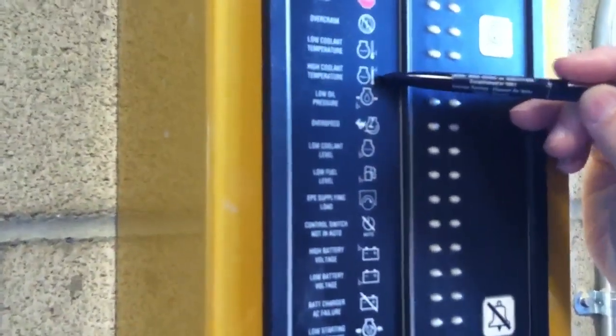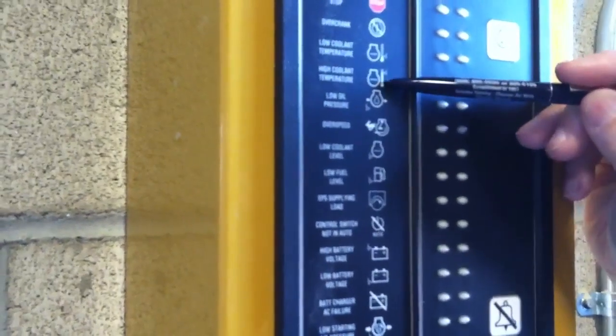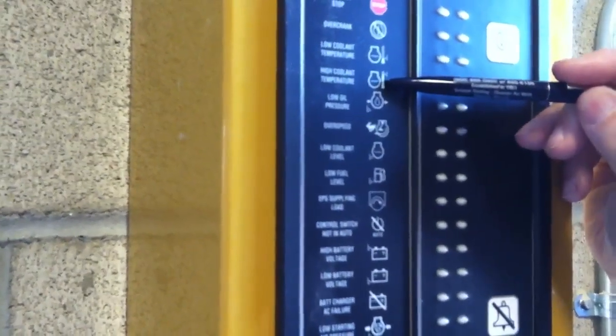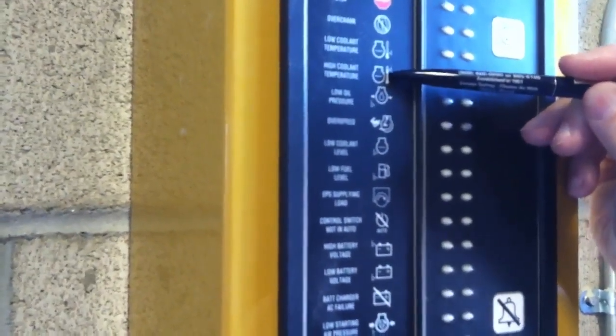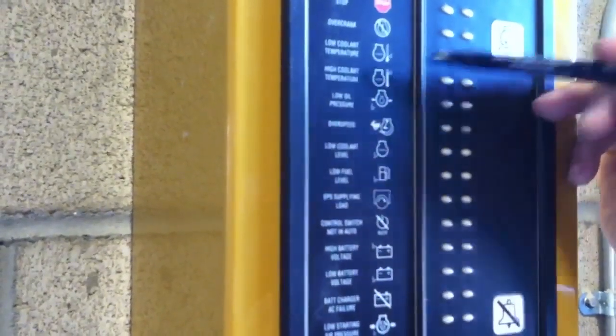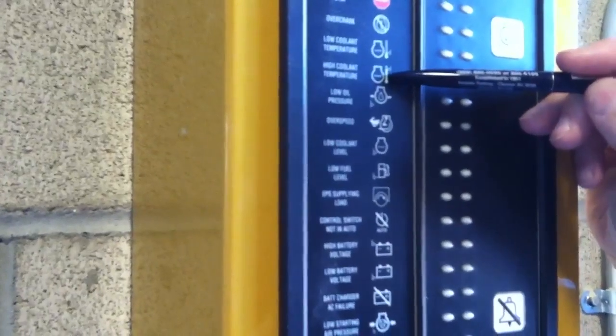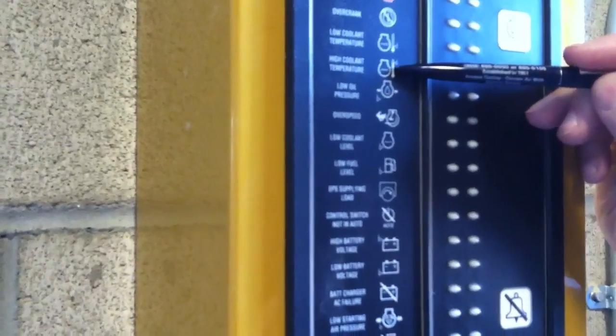High coolant temperature is a shutdown. If we go above 212 degrees we're going to get a warning and if we get up to about 217 degrees we're going to have a shutdown.